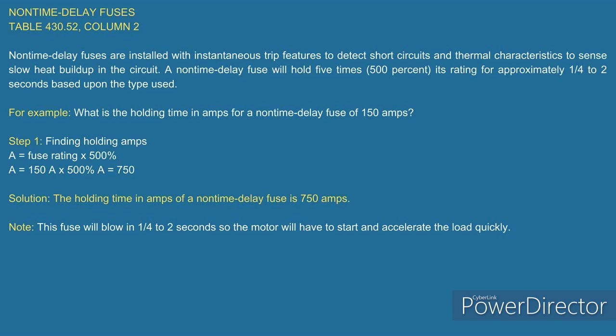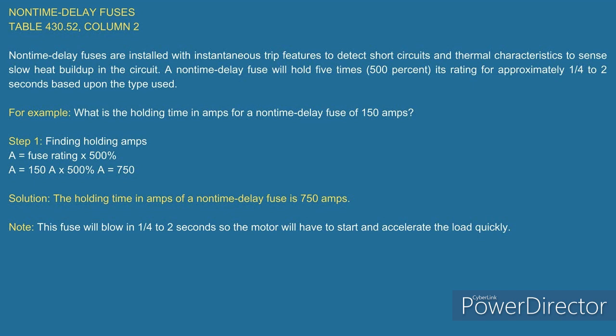But this is what you would look at, and they would tell you here that a non-time delay fuse will hold 5 times, 500%. What's that say? Just going to check the amperage. Okay. Right on. It says a non-time delay fuse will hold 5 times, 500% its rating for approximately a quarter to 2 seconds based on the type used. And this gives you an example here. If I take a 150 amp non-time delay fuse, take it at 500%, that's going to give you 750 amps.